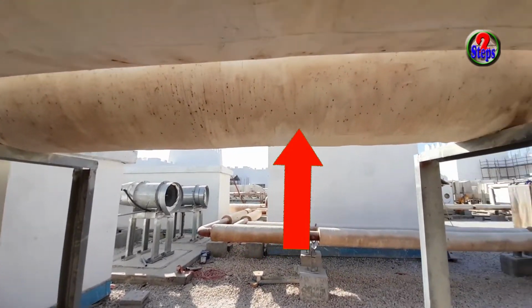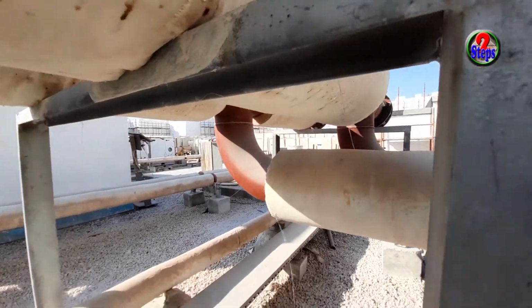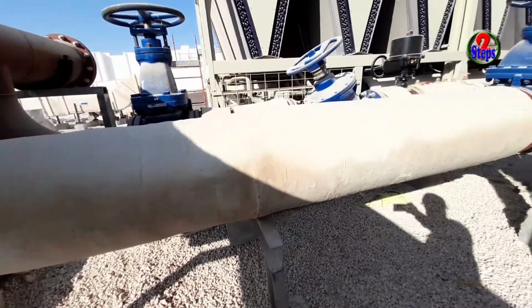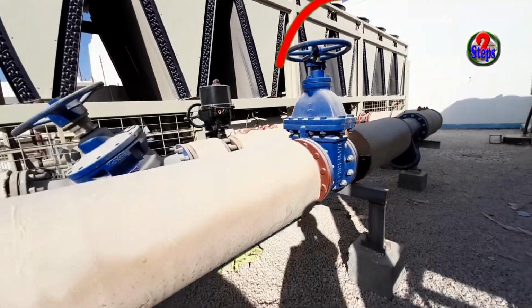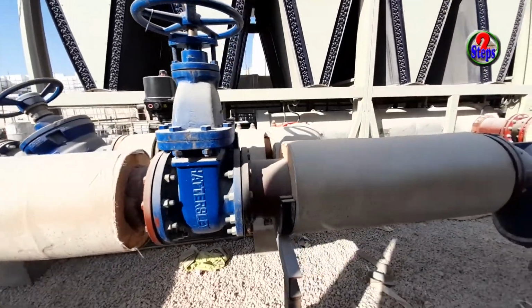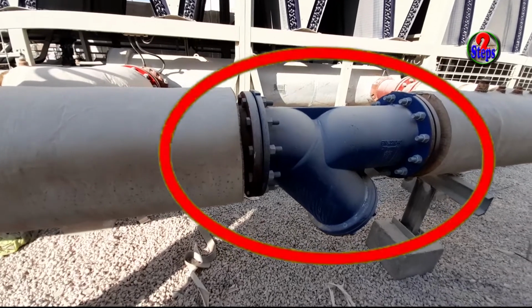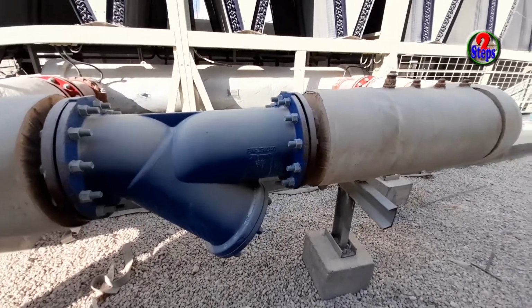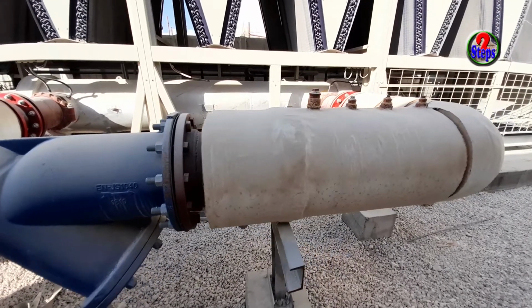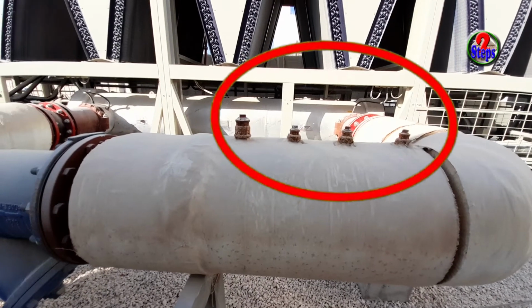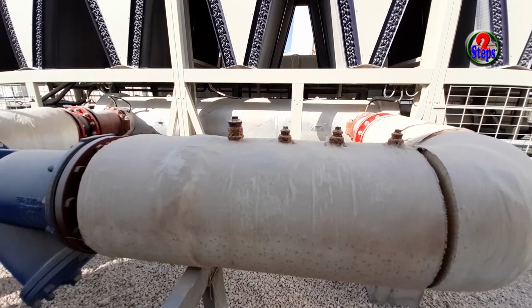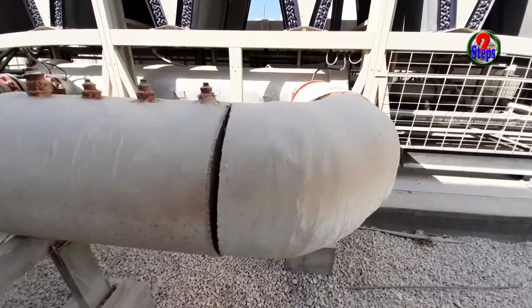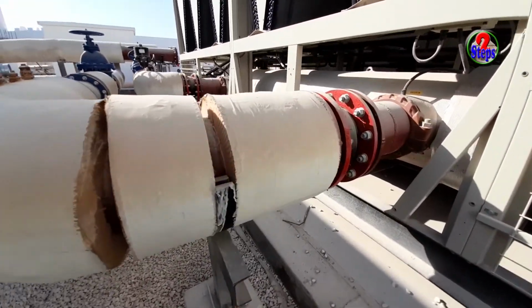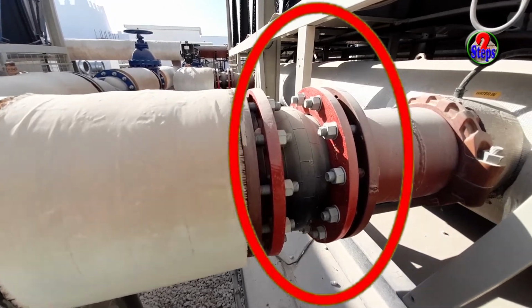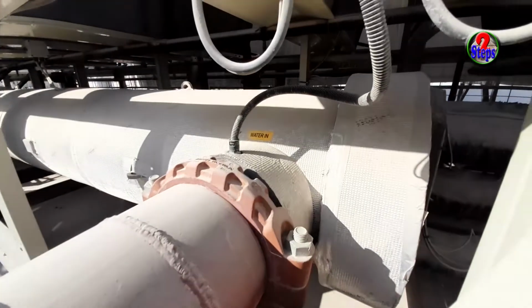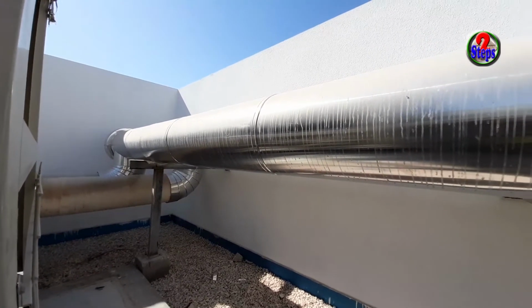This is the inlet header. Subline connected by the elbow. Then the isolation valve. Also it's called gate valve. After that, the strainer. Here is one point at the bottom of the pipe for the drain. Then some points for thermostat, pressure gauge, temperature sensor, and any special equipment. This is the flexible connector, and at the end connected to chiller inlet. Let's have a look at the final setting of a chiller inlet connection.